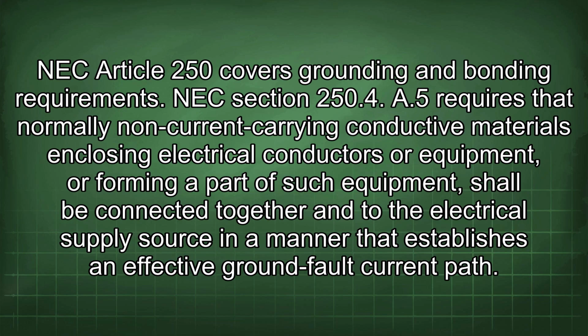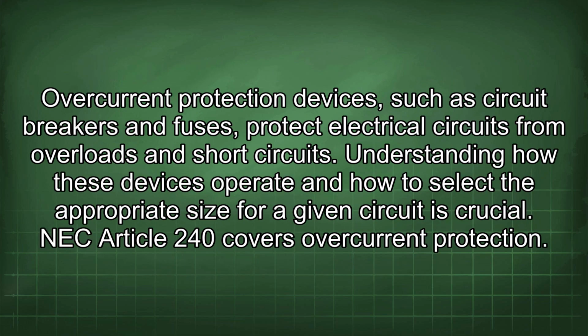NEC Section 250.4(A)(5) requires that normally non-current-carrying conductive materials enclosing electrical conductors or equipment, or forming a part of such equipment, shall be connected together to the electrical supply source in a manner that establishes an effective ground-fault current path. Overcurrent protection devices, such as circuit breakers and fuses, protect electrical circuits from overloads and short circuits. Understanding how these devices operate and how to select the appropriate size for a given circuit is crucial.